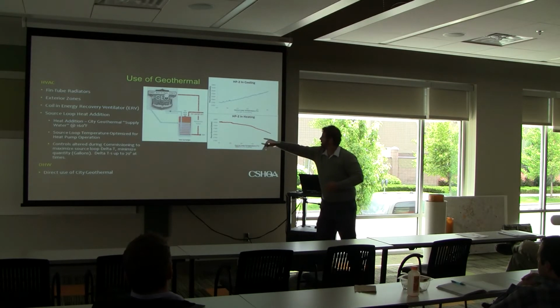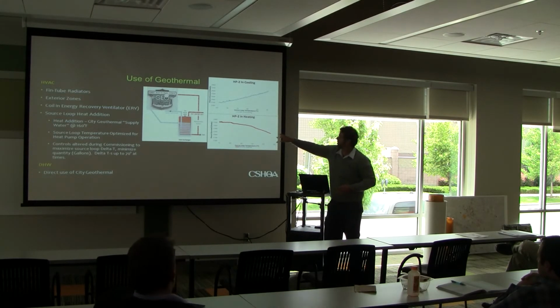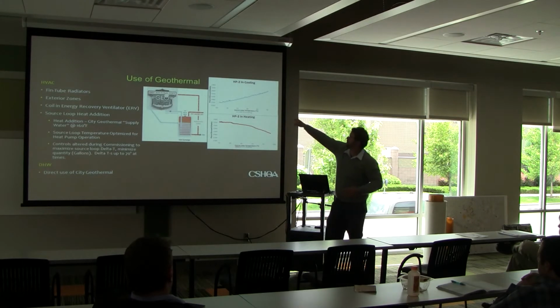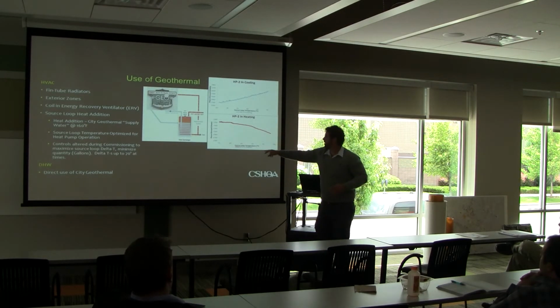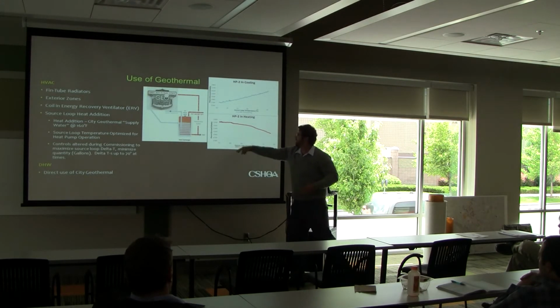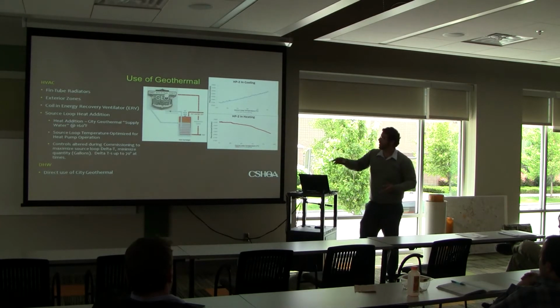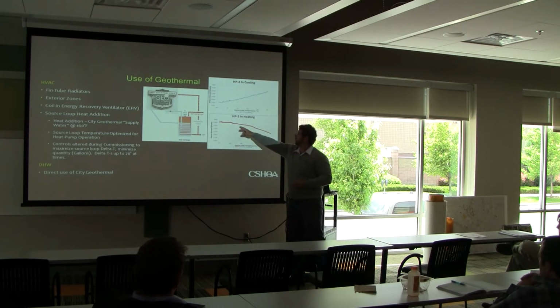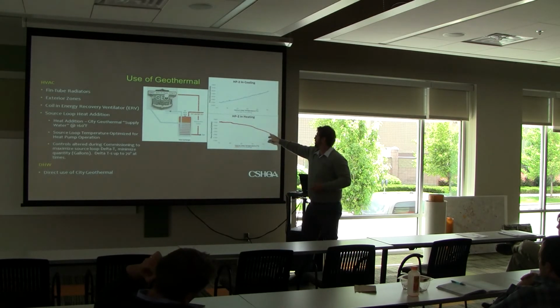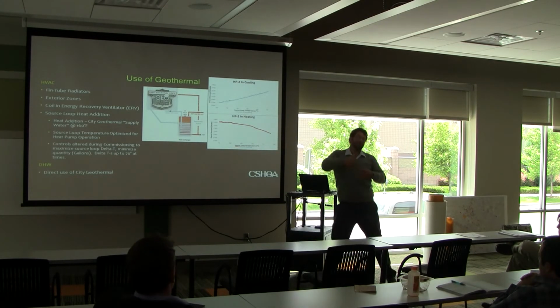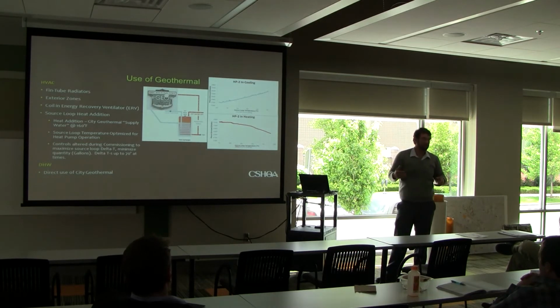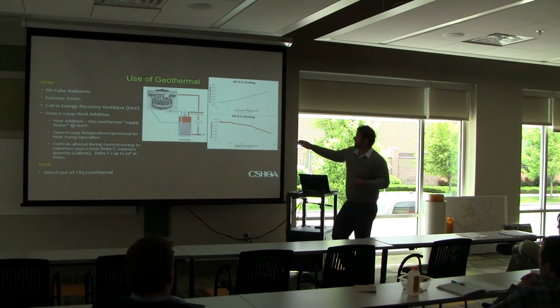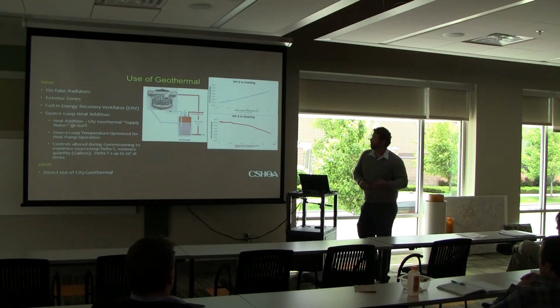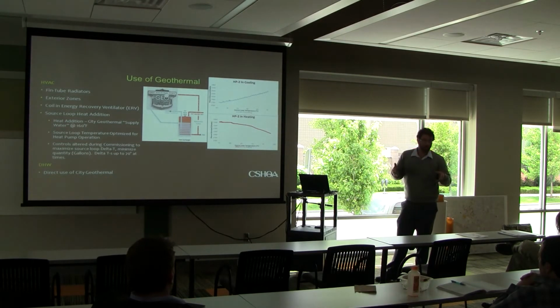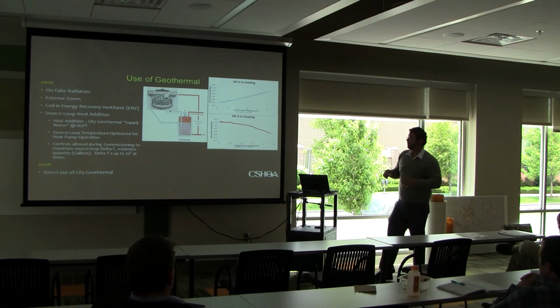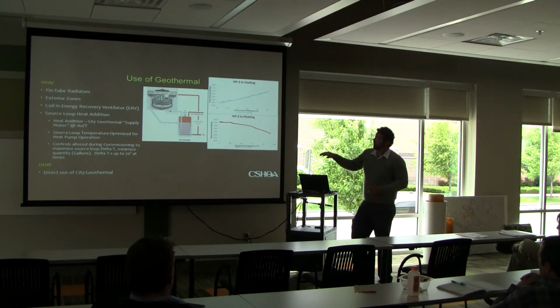But on the heating side, the slope of the line is not as aggressive as on the cooling side of the heat pump. So we found we could probably keep this at 80 degrees, even though I think design said keep it at 70, and have a somewhat decent wattage, not really gaining much if we go all the way up to 95, which would then max out what we needed to use on the geothermal side of things. So we decided on somewhere between 85 and 90 degrees to keep that source loop in the winter. In the spring and the fall, the shoulder periods, different story. So I won't get into that now.